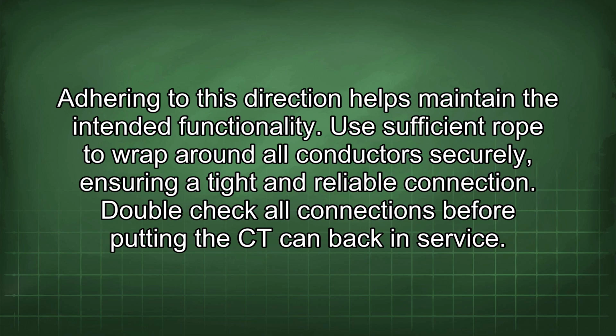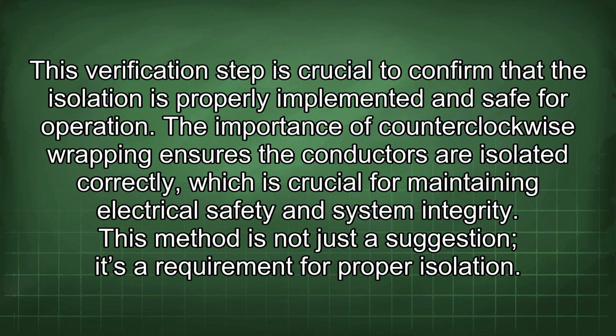Use sufficient rope to wrap around all conductors securely, ensuring a tight and reliable connection. Double-check all connections before putting the CT can back in service. This verification step is crucial to confirm that the isolation is properly implemented and safe for operation. The importance of counterclockwise wrapping ensures the conductors are isolated correctly, which is crucial for maintaining electrical safety and system integrity. This method is not just a suggestion, it's a requirement for proper isolation.